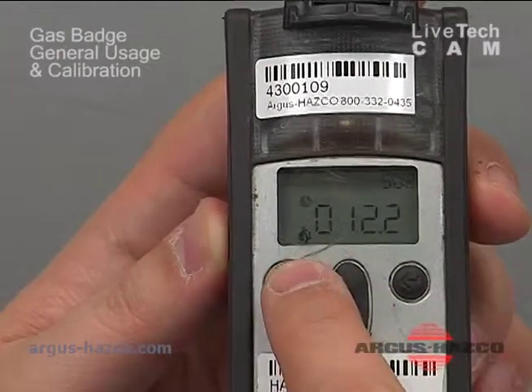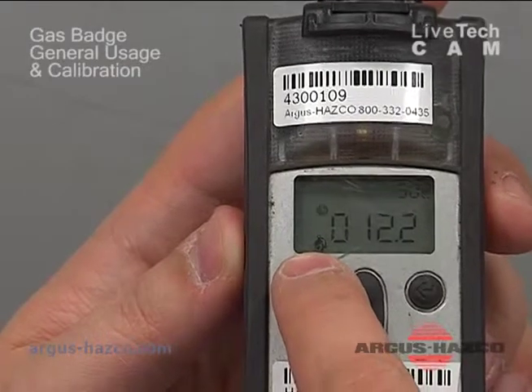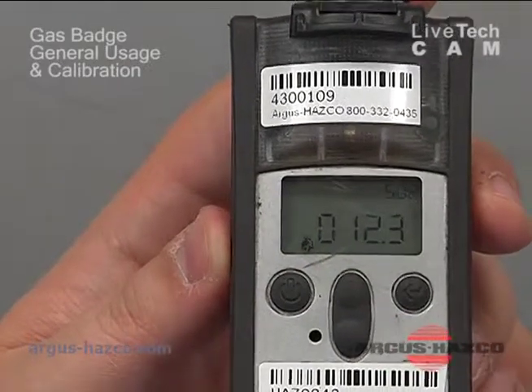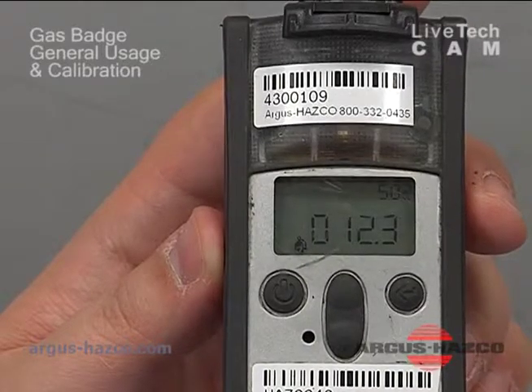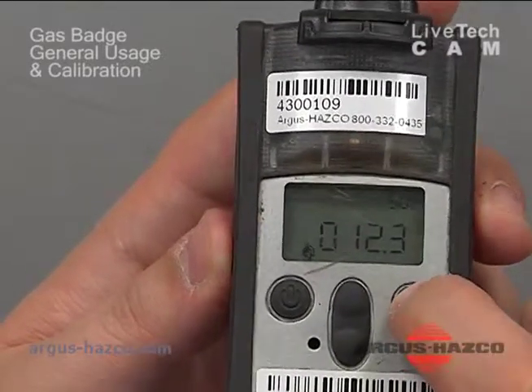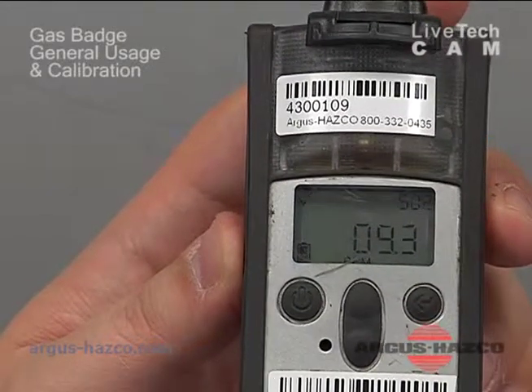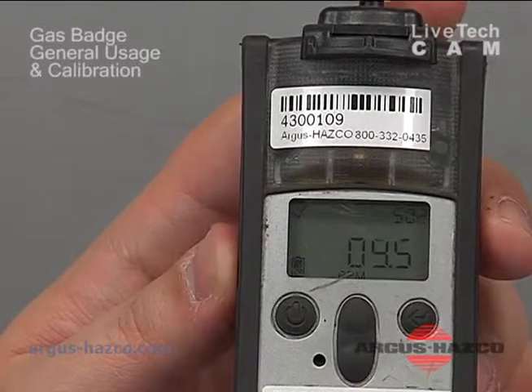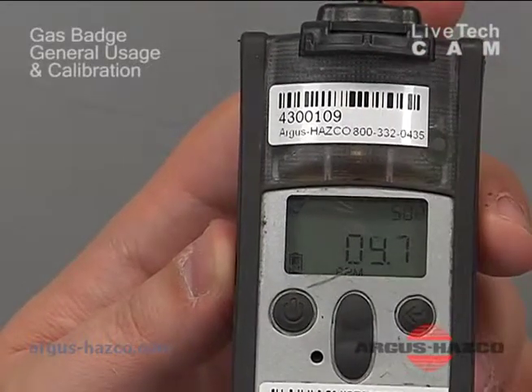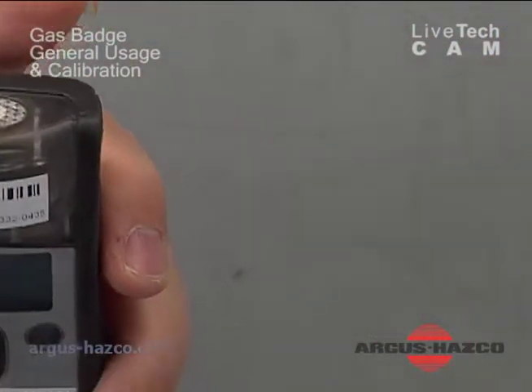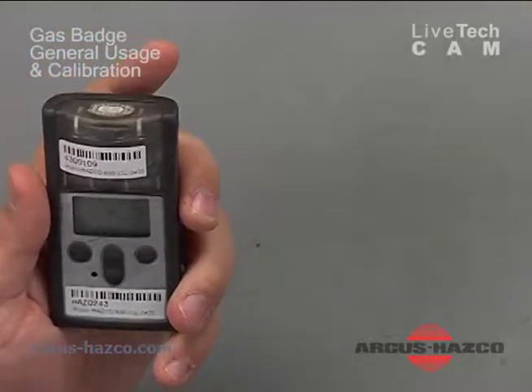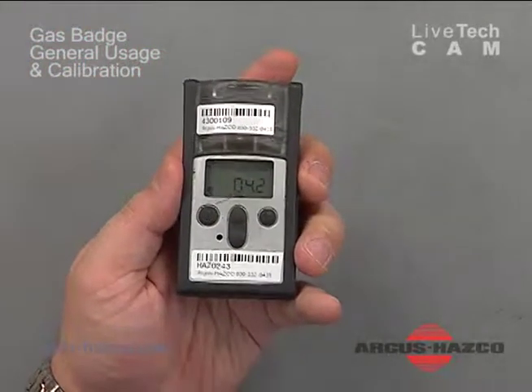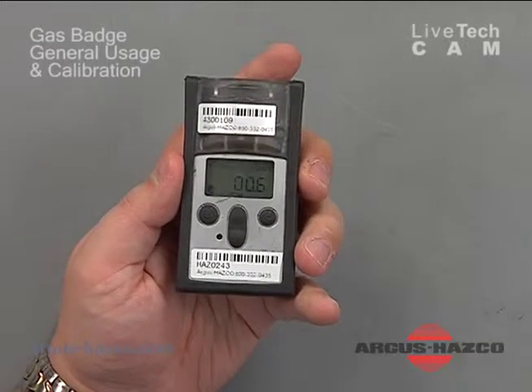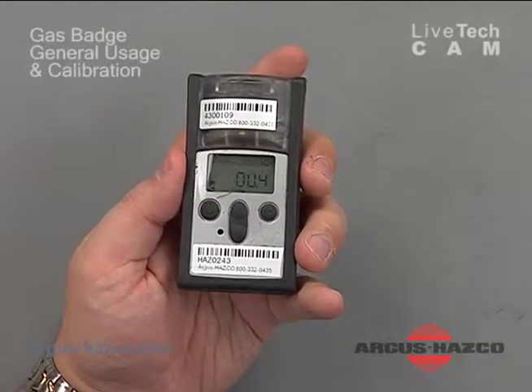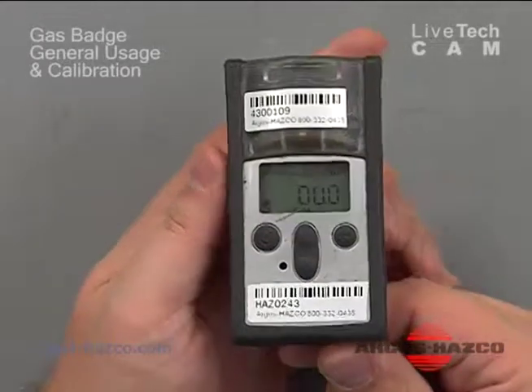And you can tell that there's a little cylinder of calibration gas there telling you that you're doing a span calibration. And it is stabilized. You hit enter. It's telling you it's CAL'd. And your 10 ppm. Take your cal adapter off. Turn off your cylinder of gas. And the reading will start to go down as it's exposed to zero air. And you'll see it drop back down to zero. And the unit is ready for use and you are calibrated.